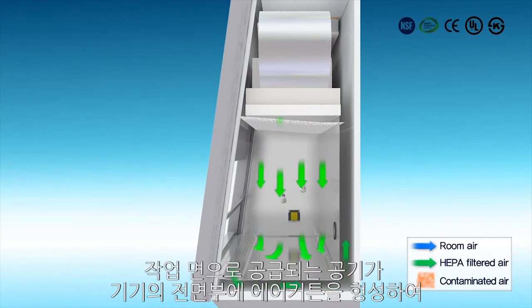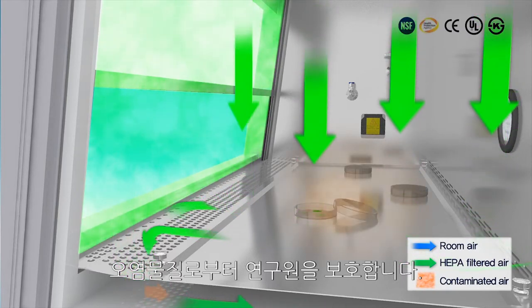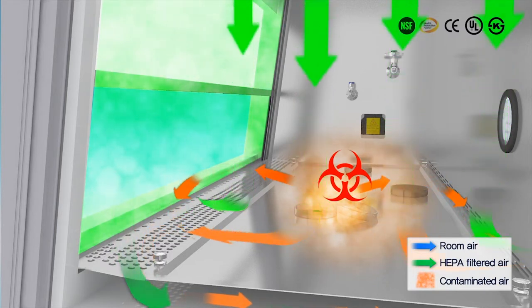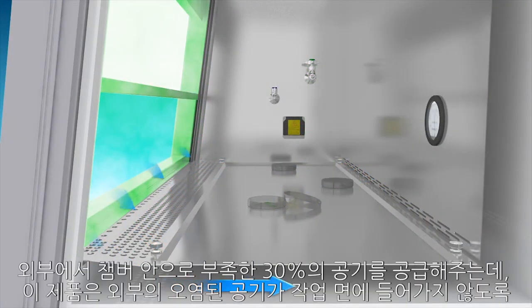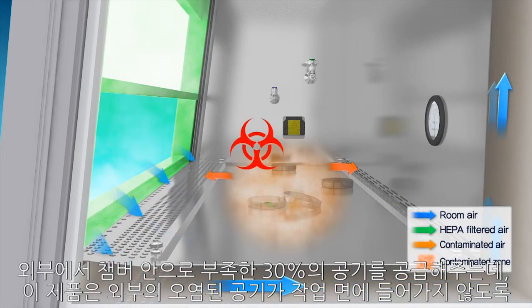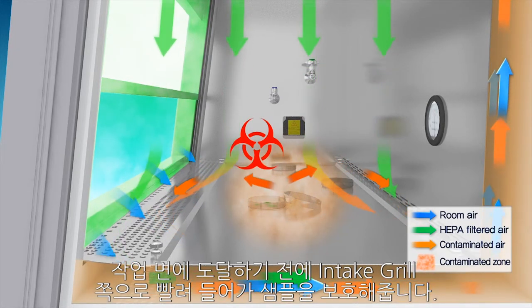The air supplied to the inside chamber protects the researcher by forming an air curtain on the front space of the biological safety cabinet. The room air will be charged to the chamber from the outside due to a 30% shortage of air, and the intake grill will protect the sample by inhaling room air before reaching the samples.